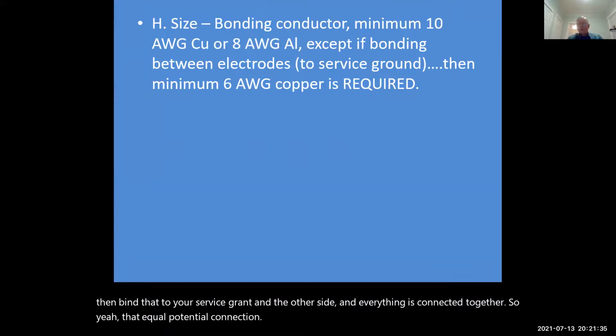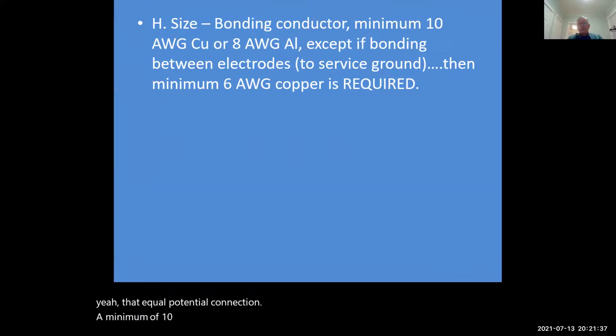A minimum of 10 gauge copper, 8 gauge aluminum, unless it's bonding between electrodes, and then a minimum 6 gauge copper is required.